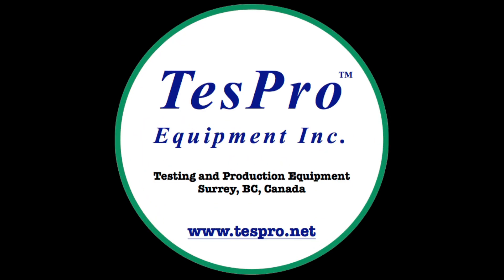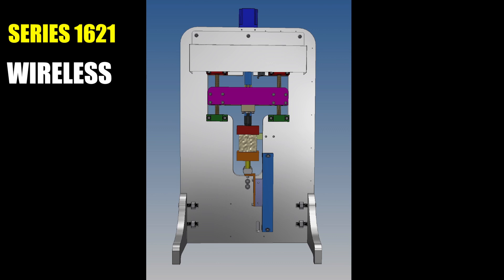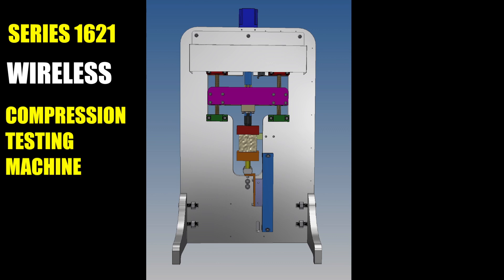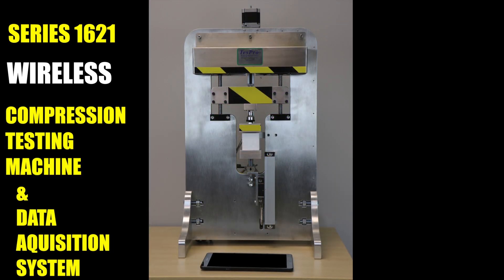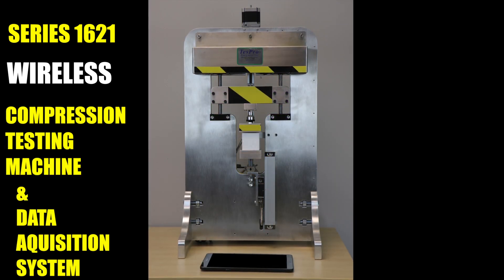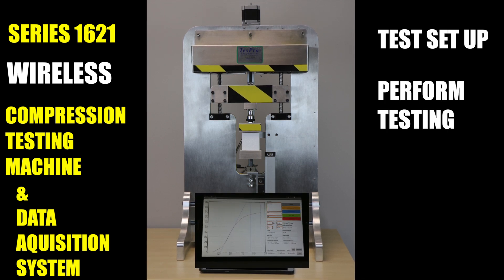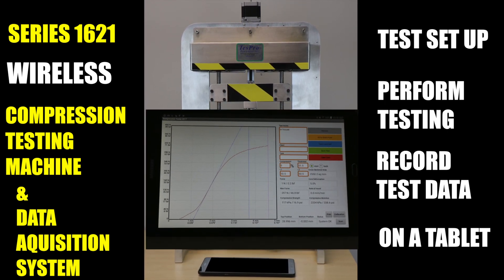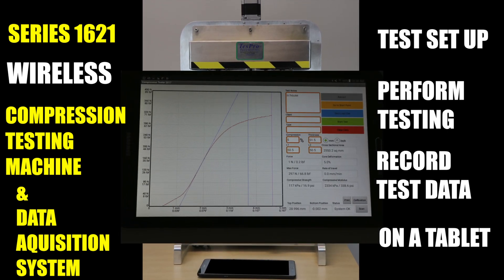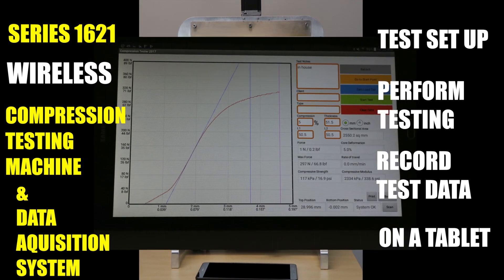The latest development in TesPro Equipment's compression testing apparatus is a tabletop compression testing machine and data acquisition system where tests are set up, performed, and test results all recorded with the input of a tablet computer and Bluetooth connection.